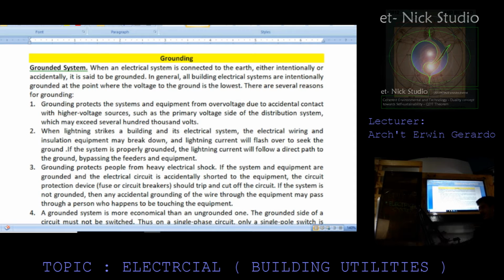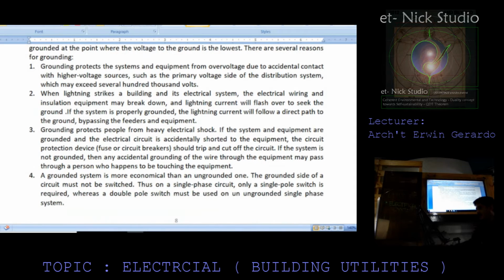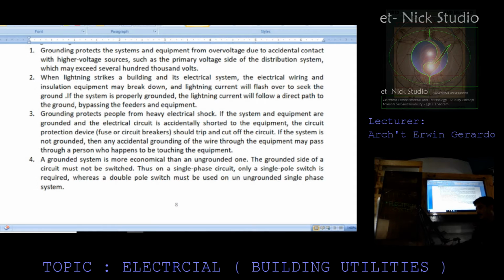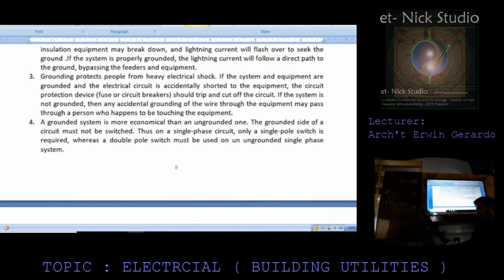Two, when lightning strikes a building's electrical system, the electric wiring and insulation of equipment may break down, and the lightning current will flash over to the ground. If the system is properly grounded, the lightning current will follow a direct path to the ground, bypassing the feeder and equipment.